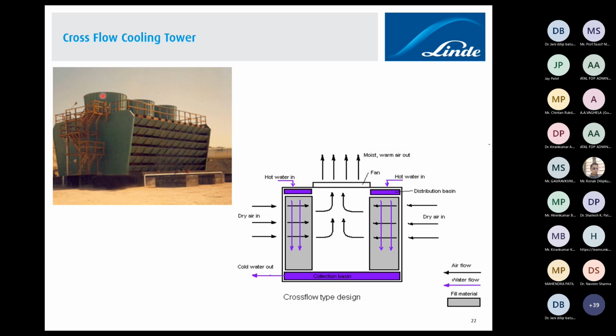Okay, so how does a cross flow cooling tower look? It's a very simple one. It is a 3-cell cooling tower, wooden and FRP cooling towers are there. These are the side louvers where air entry is there, and this is the construction. Here you will see the cooling tower sump. This is a basin which is at the bottom of the cell. Sometimes you will find a partition between the cells, so that during maintenance, when you want to completely shut down one cell, you can stop the spraying of water and stop the fan, and you have a partition, so you can carry out basin cleaning like that.